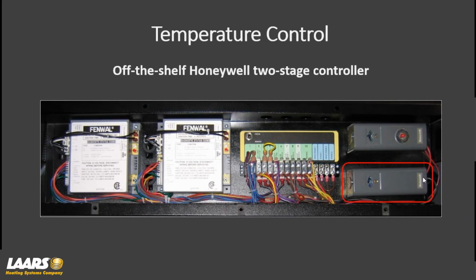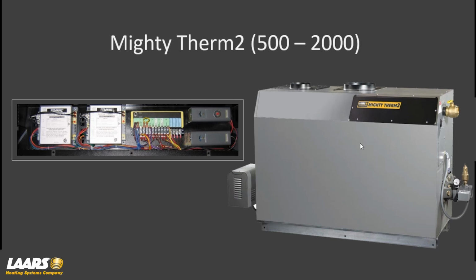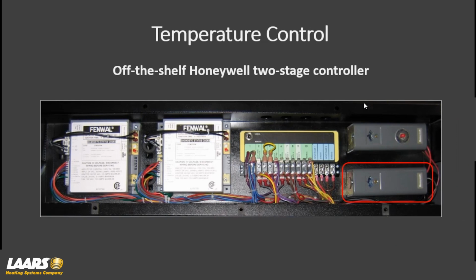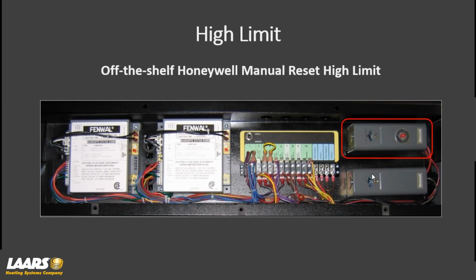Now, we use an off-the-shelf 2-stage control. By the way, the MightyTherm2, all of these are 2-stage operation, from the 500,000 all the way up to the 2 million. So it's 2-stage. Your Pennant could be up to 4 stages depending on the size of the boiler. So again, we use an off-the-shelf 2-stage control. Very simple. Your adjustments are made there. Hypothetically, you need 160 degrees out to a system loop. We have a jumper here. It's in yellow on this image. And every boiler leaving the factory will have a jumper on them. Currently, they're a red wire, and that is your TT enabled. Okay, so a hydronic application, you could use maybe energy management or something, gives us a call for heat, and then we're going to operate on the outlet sensor as a 2-stage control. Okay, we also have a manual high limit.